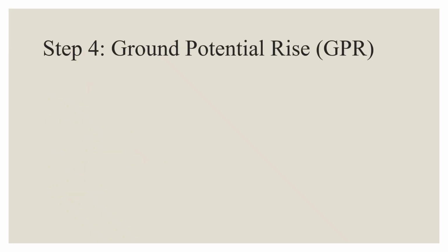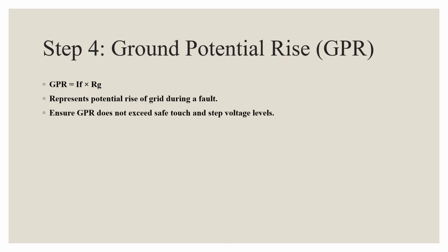The fourth step in designing is to calculate the ground potential rise (GPR). The ground potential rise, or GPR, is given by multiplying fault current by grid resistance. It represents how much the grid potential increases during a fault. We must ensure that GPR does not exceed the safe step and touch voltage levels. Otherwise, a person standing near grounded structures may be exposed to dangerous voltages.